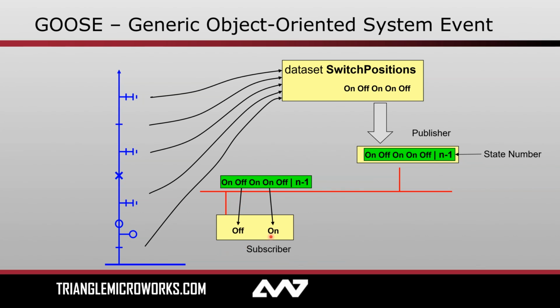A good thing to point out on this slide is that it's very common to have extra data in your GOOSE control block, more than you need for any one particular device. Maybe the next device down the line cares about the first value or the third or the last one, but this particular device only needs to grab these two values. I can package all of that data up into a single GOOSE message, knowing that only certain subscribers care about some of it. Now, a short time later, one of my switches changes from open to close. This is reflected in the data model for my device, and within a couple of milliseconds, it's pushed out on the wire. Now my state number has incremented from N-1 to just N. This is published on the wire, and the subscriber receives the updated data from this new message and includes it in its internal data model, which it needs to use for control functionality or protection, whatnot.